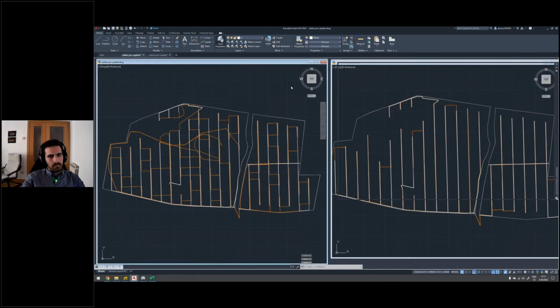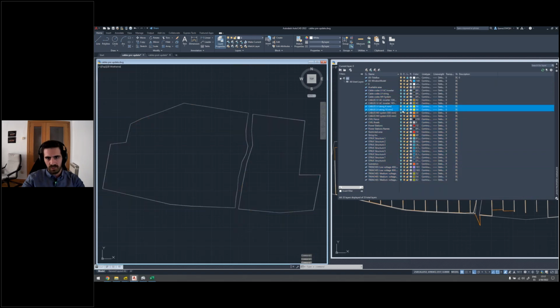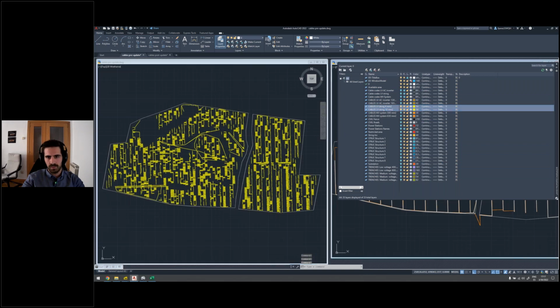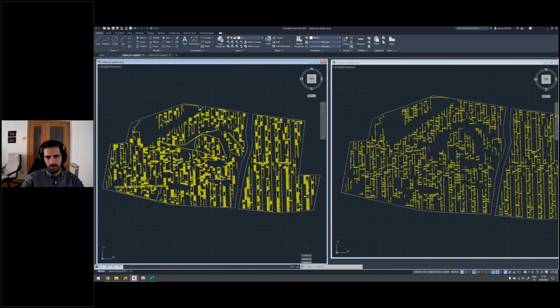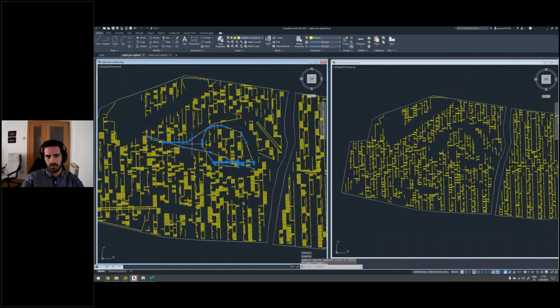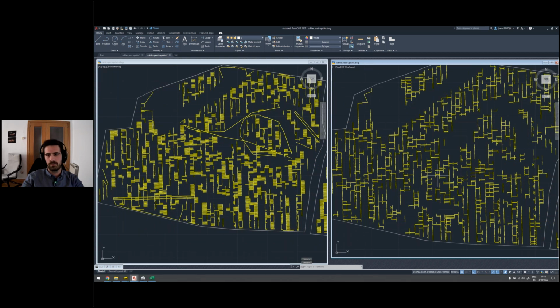And finally, I don't know if it's going to be easily visible, but maybe we can try. I want to show you the low voltage system in both designs because it should be different. We will see if we actually can see the difference or not. Right. So what I'm showing you here are the string cables. The cables are 4 square millimeters and 10 square millimeters in some cases. As you can see, while the designs look more or less similar on the surface, we had some cables which were, again, doing really weird things around structures. Also, we had some errors here. And the new algorithm doesn't have any of that. So this is obviously a great improvement where the cable lengths are going to be much better. The sections aren't going to be affected.